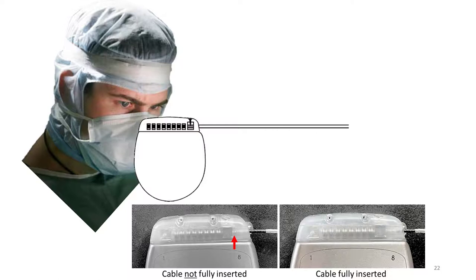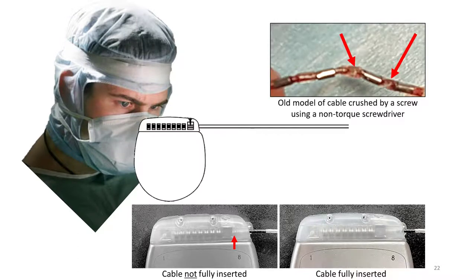However, when dealing with non-hybrid systems, it is sometimes suggested to do the reading before locking the screw, in order to avoid possible injuries to the cable if the screw is tightened over the wrong part of the cable. However, I believe that this risk is small if you look at what you are doing, and on rare occasions locking the screw will change the location of the cable, or at least the reading enough to affect the impedance, so I prefer to measure this only after we have locked the screw.